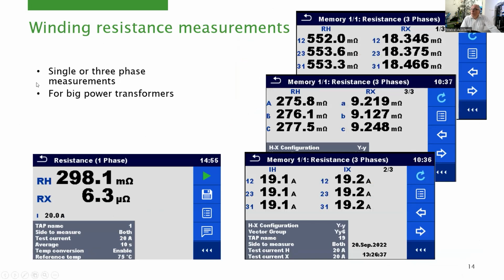On all sizes of transformers, from single phase to three phase transformers, different configurations are possible to test. Here is the screen of results of a one phase transformer. You see values immediately in different ranges. Usually you can set up the parameters. Here on the right side we have the output of measurement of the three-phase transformer, where you have much more data which can be output of the measurement. Also, I will explain later, results come in two forms. You can see the current and all other values for the low voltage side and for the high voltage side.